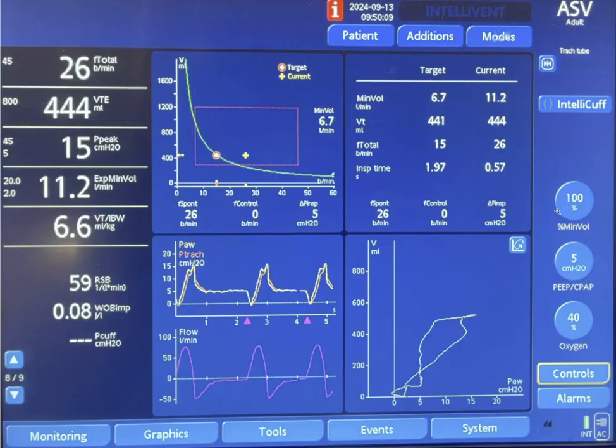So the machine will determine the optimal respiratory rate for the patient. This is done based on calculation of the RC which is time constant resistance multiplied by compliance.